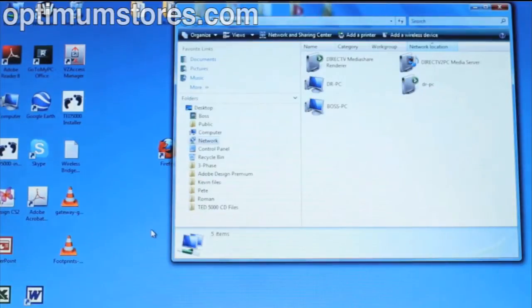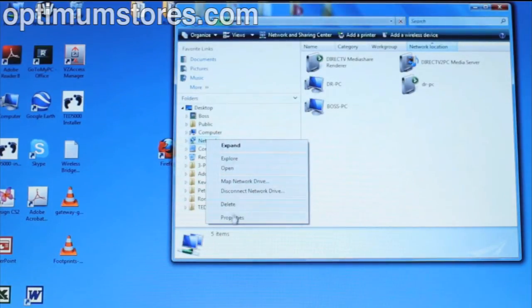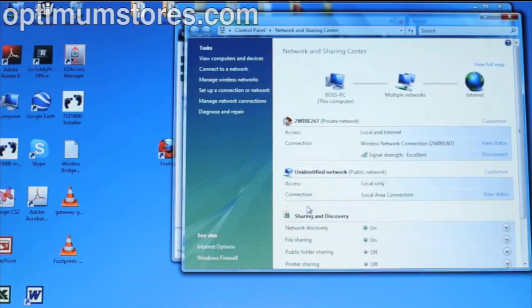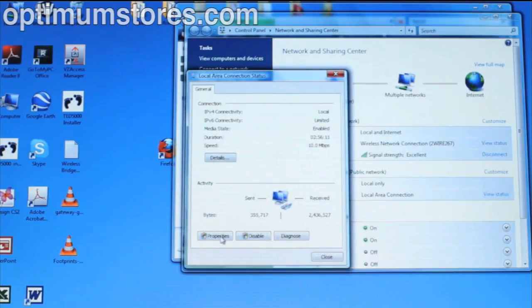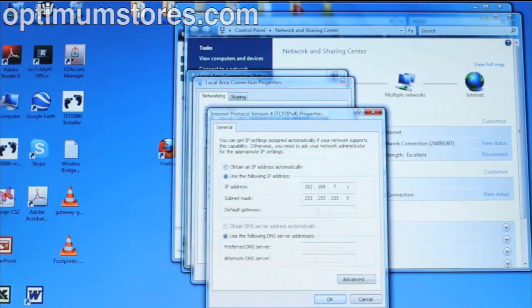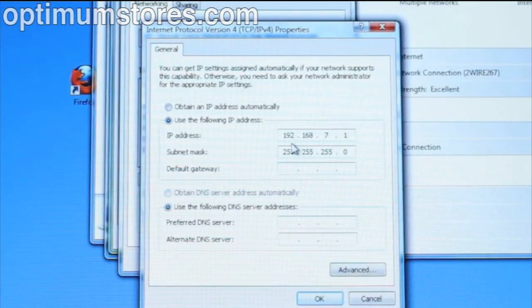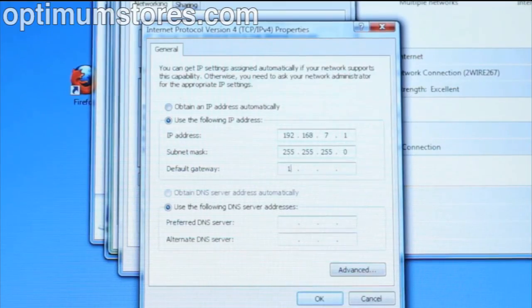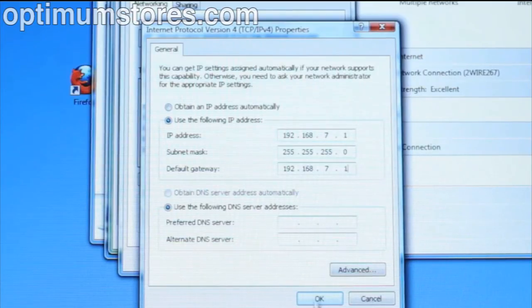We are now ready to proceed with a direct connection. Once your computer is ready, connect the Ethernet cable from your gateway directly into your computer. Although the paths may vary depending on your operating system, go to your computer, then Control Panel, then Network Settings, next click Local Area Network and select Properties. Next, select Internet Protocol. If there are multiple Internet Protocols, select Version 4 and select Properties. Note the current settings so that you can return to them later. Change the IP address to 192.168.7.1, the Subnet Mask should be set to 255.255.255.0, and the default gateway should also be set to 192.168.7.1. Do not change the settings for DNS Server and click OK.